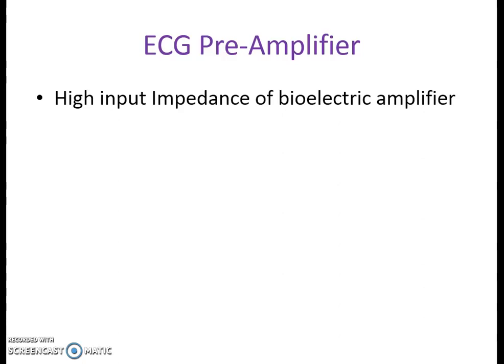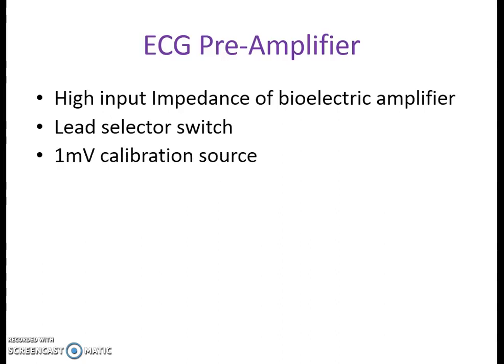One of the most important parts of the ECG machine is the ECG preamplifier. Whenever we are using a preamplifier, we have to look for certain important characteristics. The first and foremost is that it should be a bioelectric amplifier having high input impedance. This characteristic enables the preamplifier to deal with very small amplitude signals and ultimately eliminate the loading effect. The preamplifier should have a lead selector switch and a 1 millivolt calibration source, because the machine used for diagnosing patient abnormality must be calibrated. So before each reading, we generate a 1 millivolt calibration pulse from the machine itself.